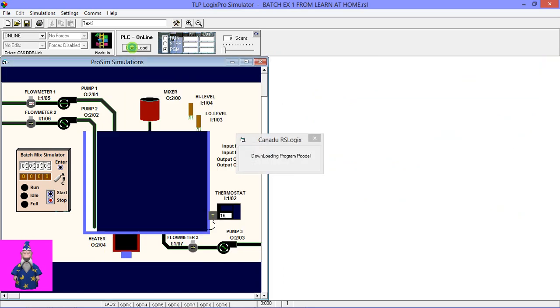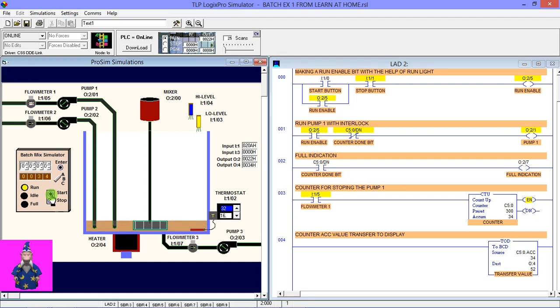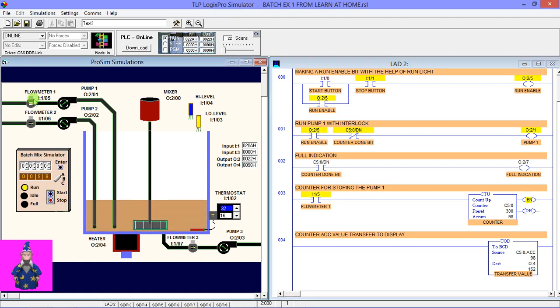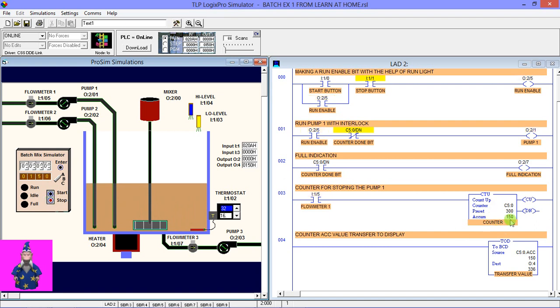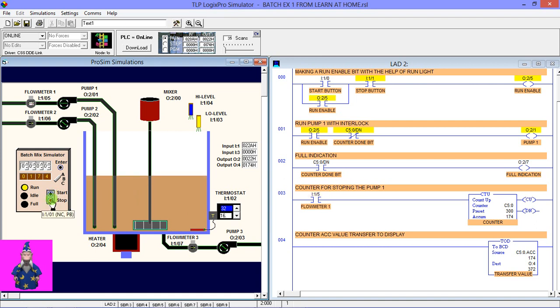Now just download this program, go to run mode, and check whether it is working or not. When I press the start button, here you can see the tank is filling, the pump one is running, flow meter is running, and the counter value—you can see its accumulator value is increasing. You can also see the accumulator value here. And when I press the stop button, here you can see the process is halted immediately. When I once again press the start button, the process will run again.